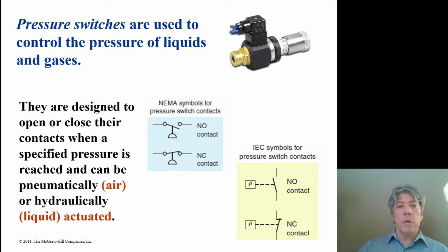And what those switches do is they prevent the system from operating if the pressure is too high or too low. Now you might wish that it would operate anyway, but the purpose of these switches is just to make sure that the machine does not destroy itself, right? That it doesn't damage itself, because in refrigeration systems, often the oil, and in fact every one that I know of, the oil is mixed in with the refrigerant, so the refrigerant has to flow around, and if you don't get oil to the compressor, it's going to burn out.